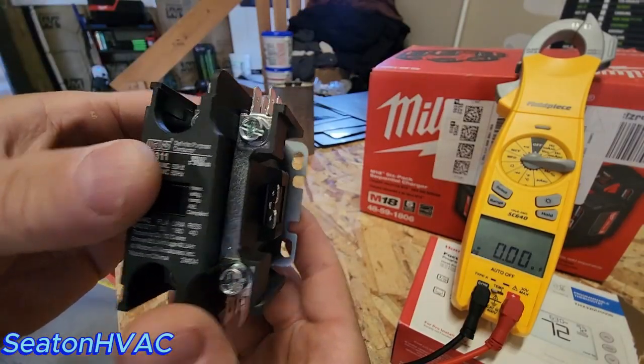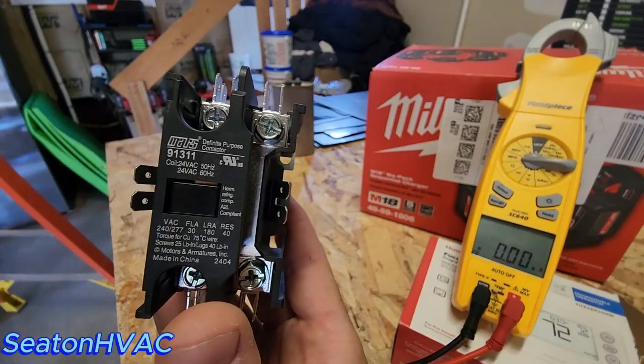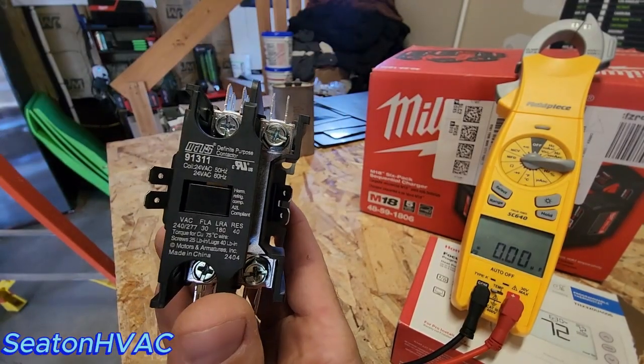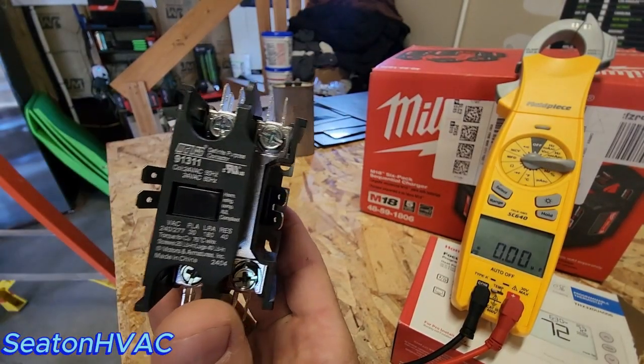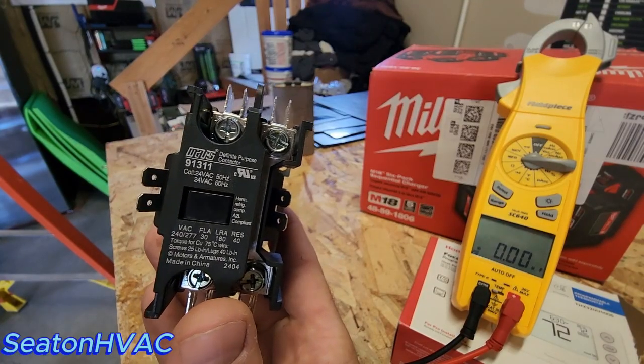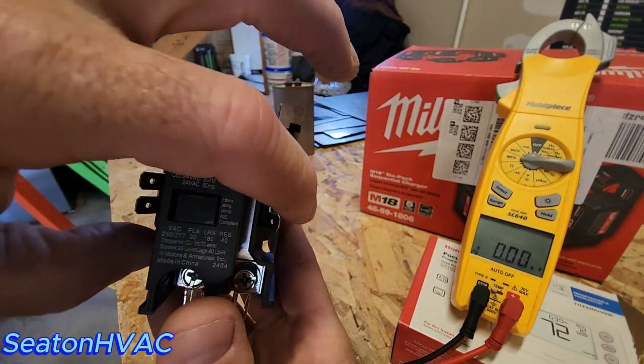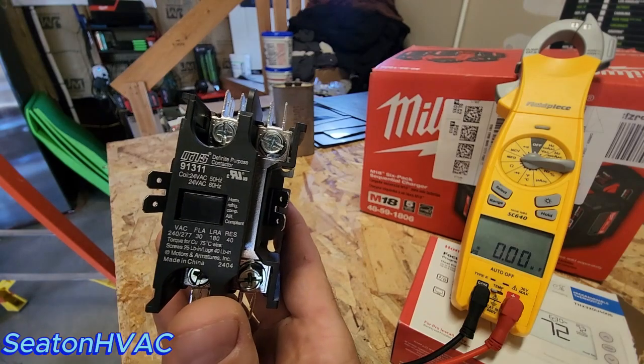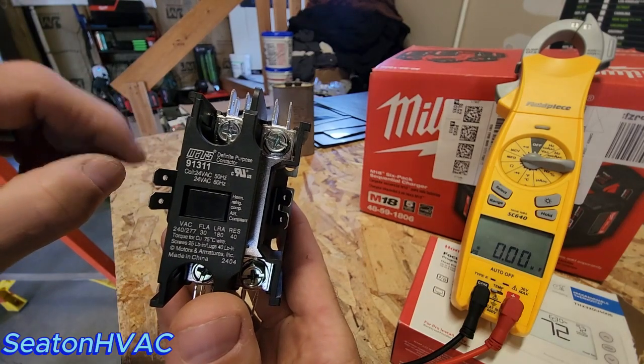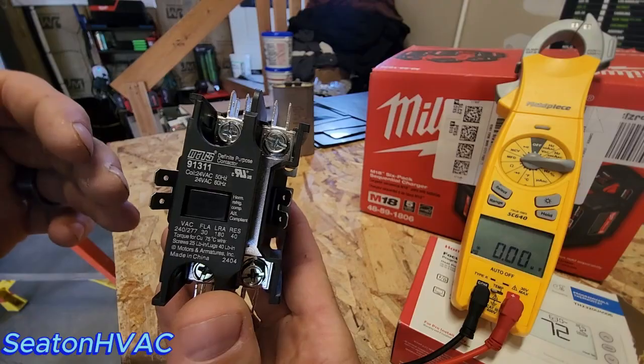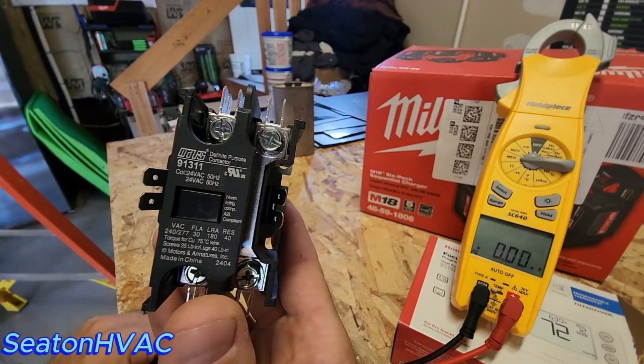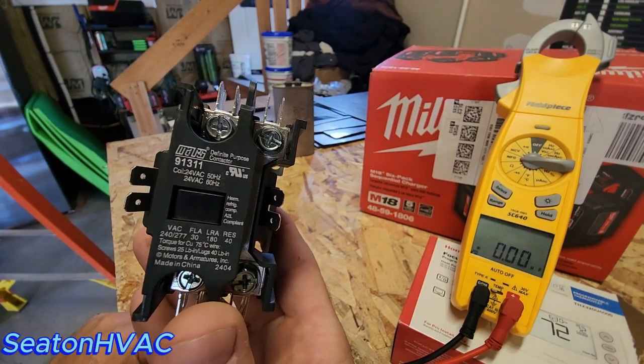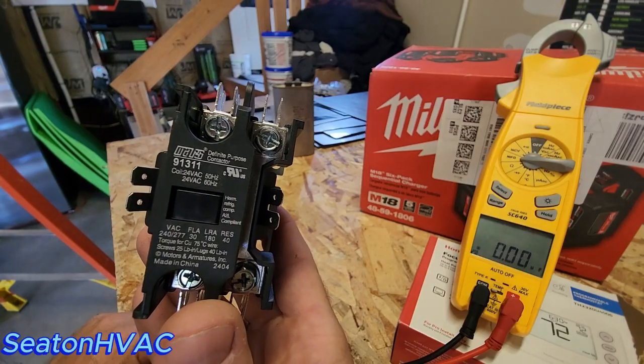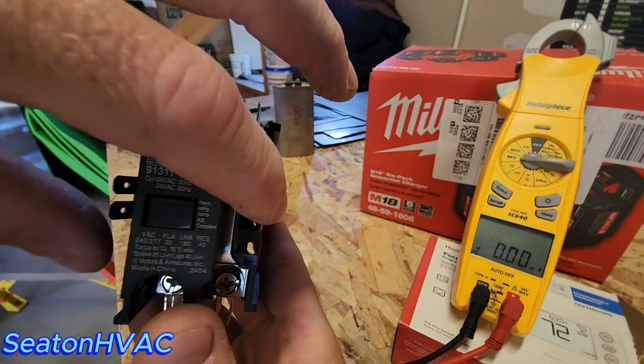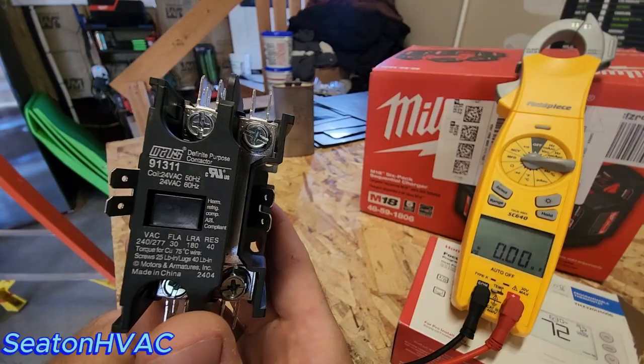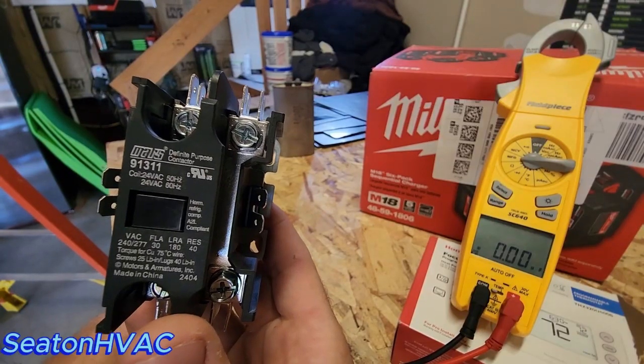So what you do, let's say you walk up on a piece of equipment, you pull your 2 low voltage leads off. Make sure they don't touch anything. If you don't feel comfortable doing that with it live, go inside and shut off your indoor unit. That'll kill the 24 volts coming to the coil. Okay. Or you could also take the Y and common wires coming into the heat pump or AC, and disconnect those. Just disconnect the wire nuts and just make sure they don't touch anything, obviously, and then you're not energized. Pull these off, and yeah, you don't want load on the coil as you test it.